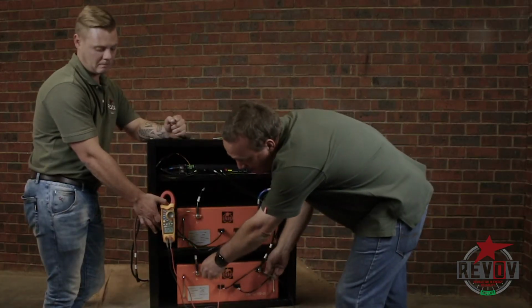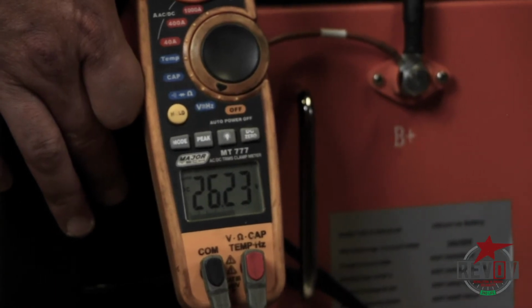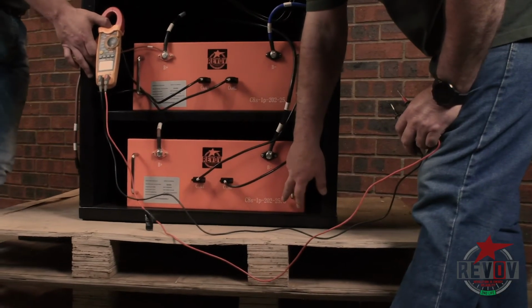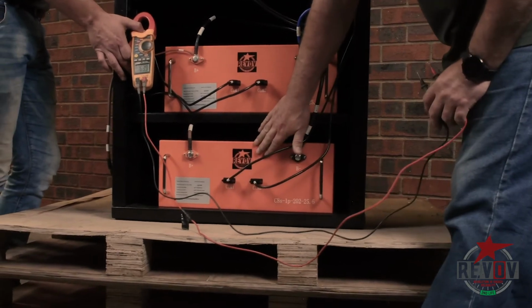If I measure battery 1, it gives me a reading of 26.24, which is 100% correct. The flat of this is 25.6 nominal, so this battery is practically full.